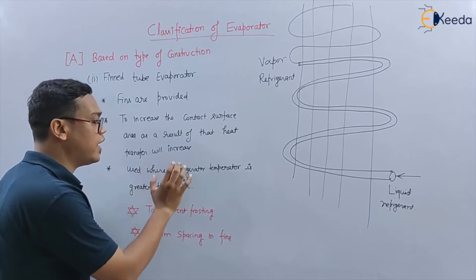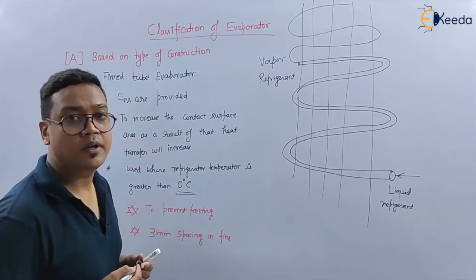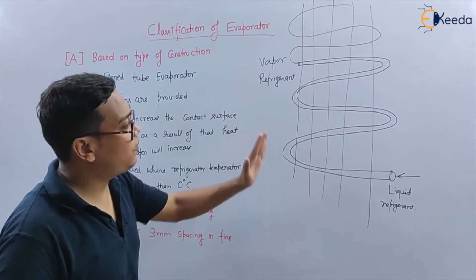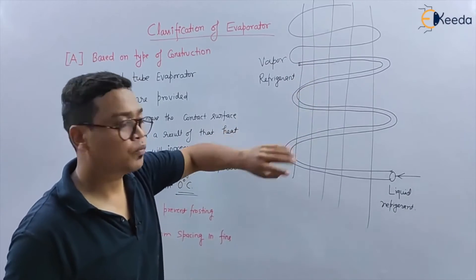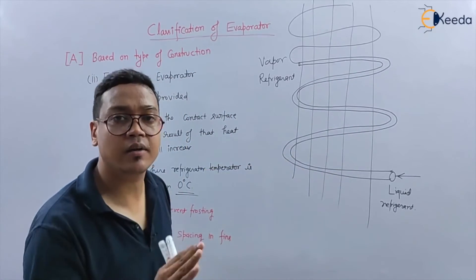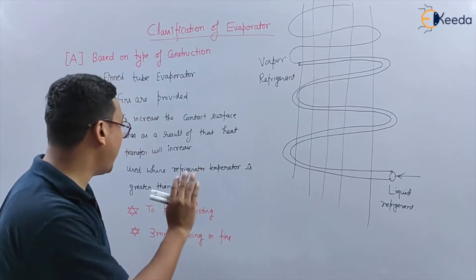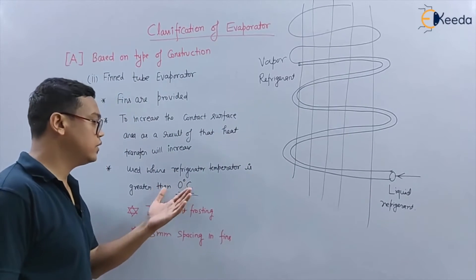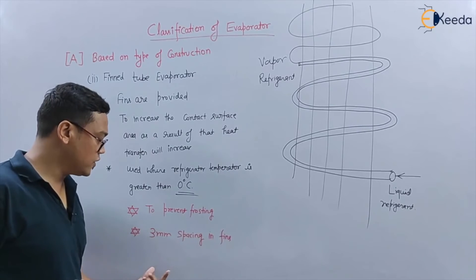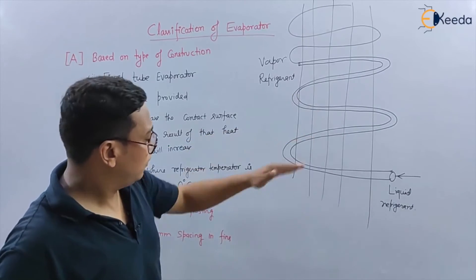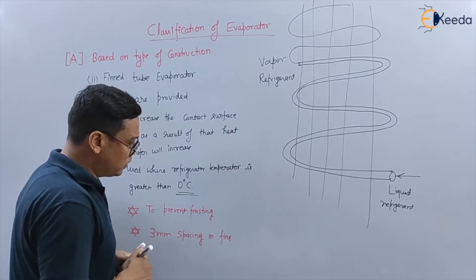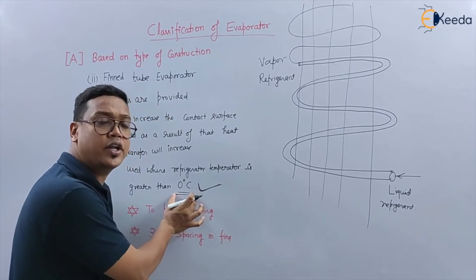The fin tube evaporator is used where the temperature requirement is greater than 0°C. If the temperature is less than 0°C, frosting will occur in the evaporator — ice will accumulate between the fins, blocking airflow. To prevent frosting, fin spacing is kept larger. That is why these evaporators are used where the temperature requirement is greater than 0°C.